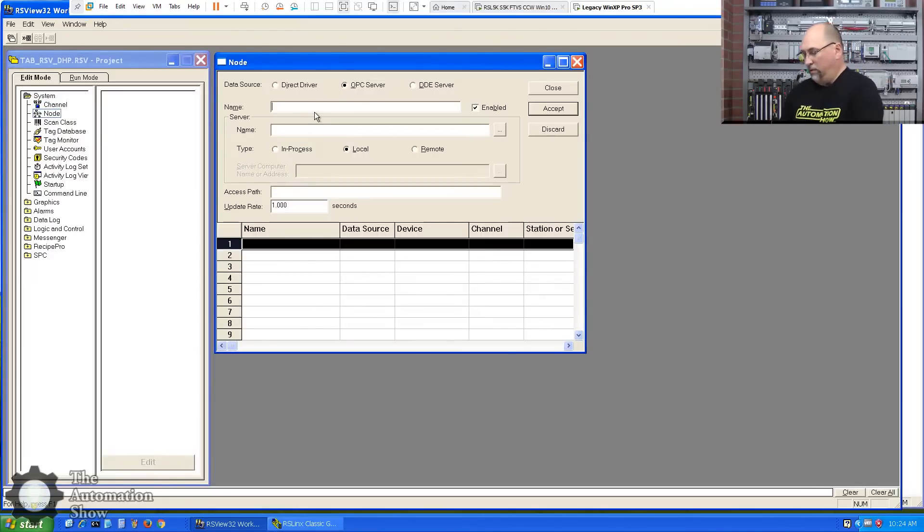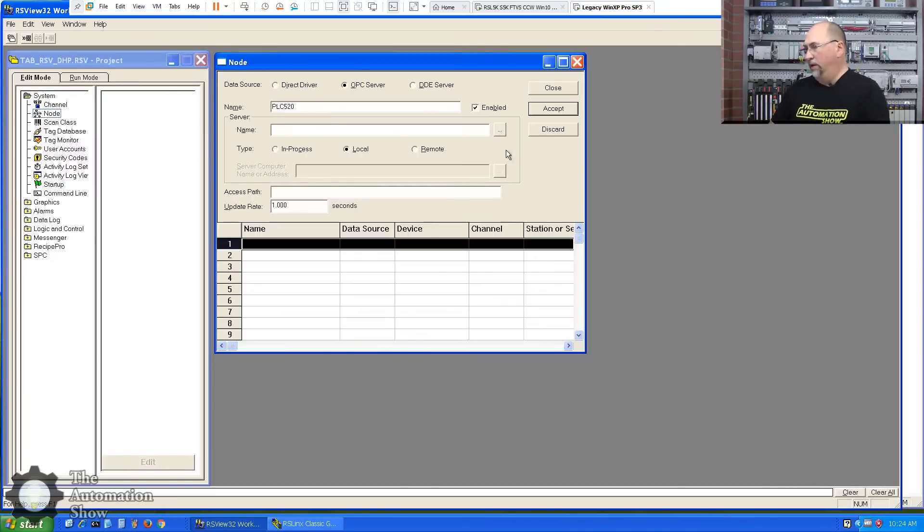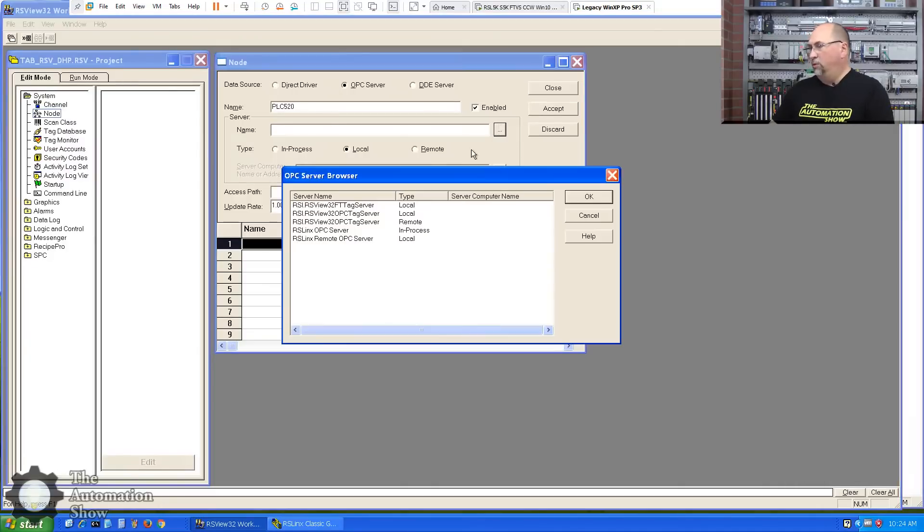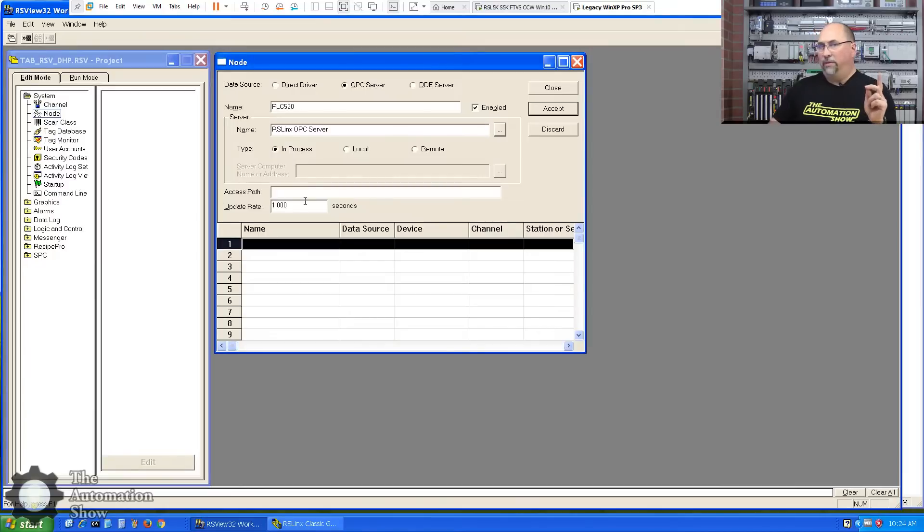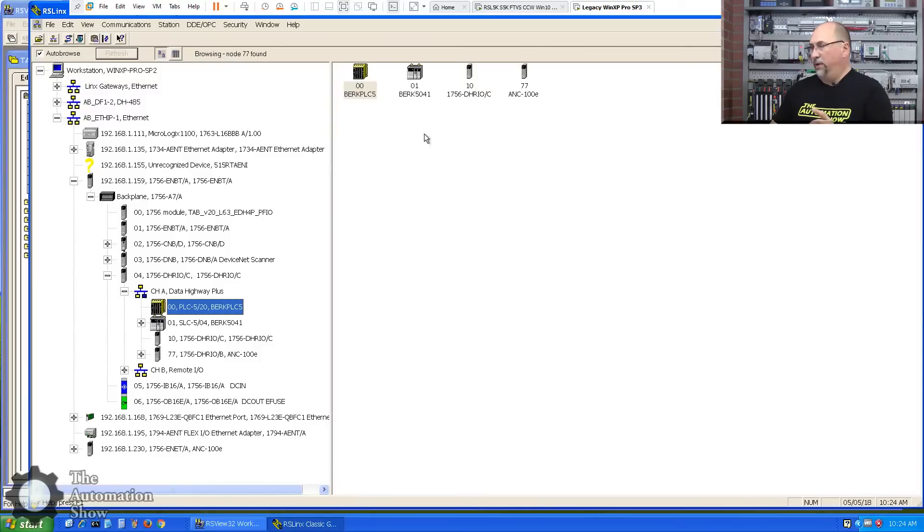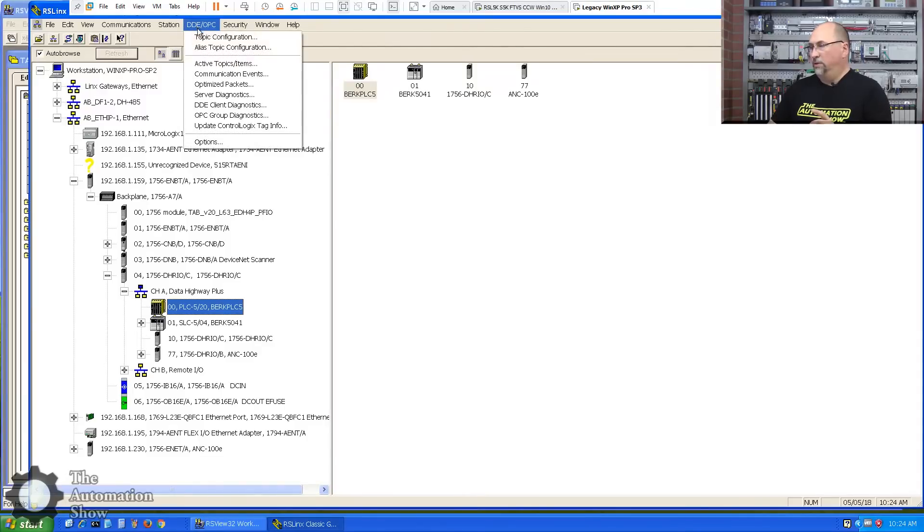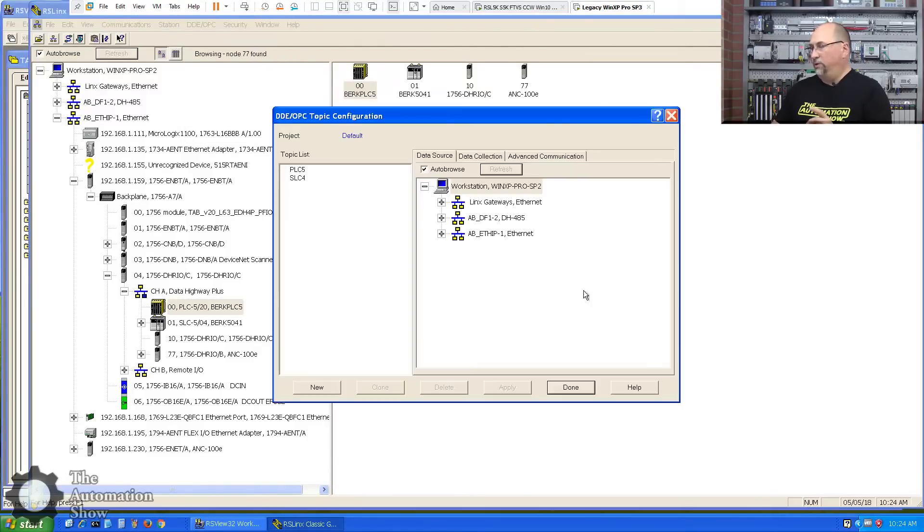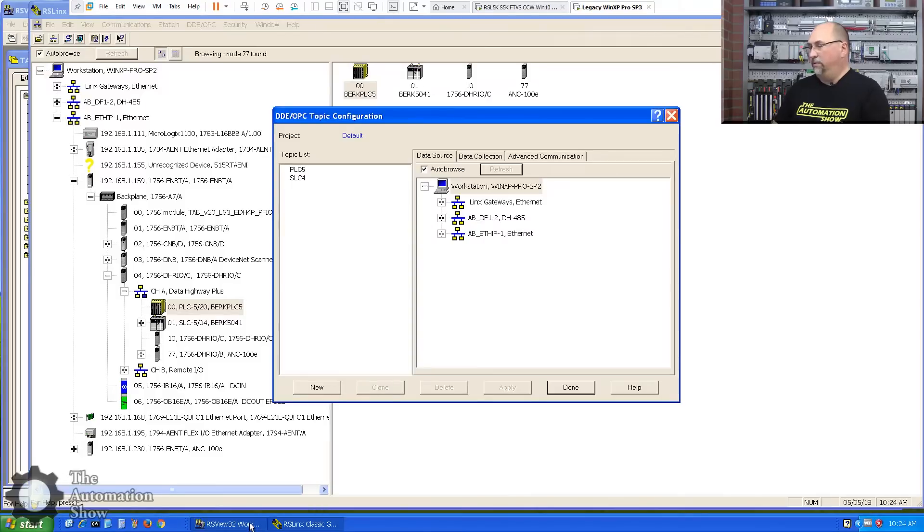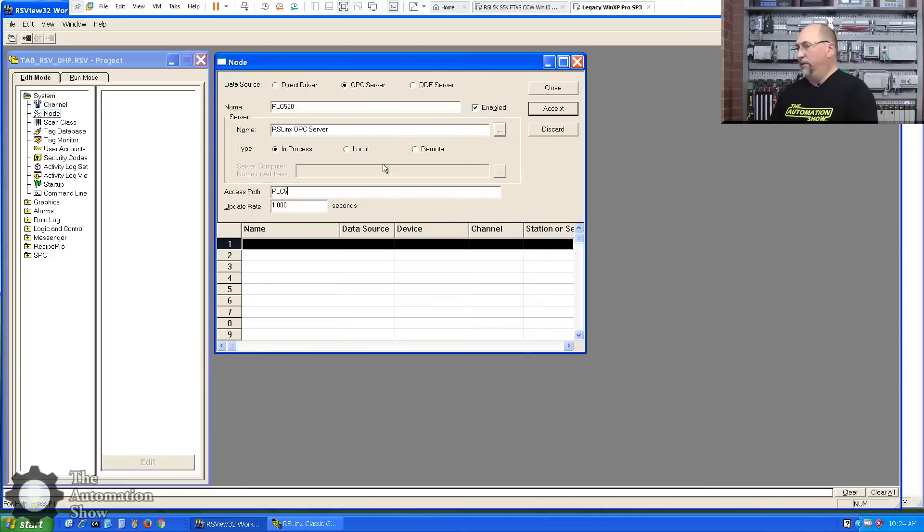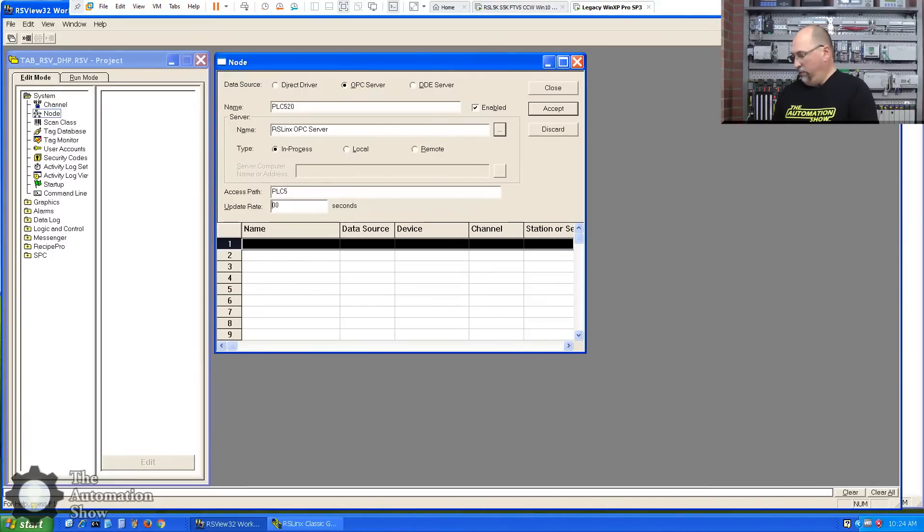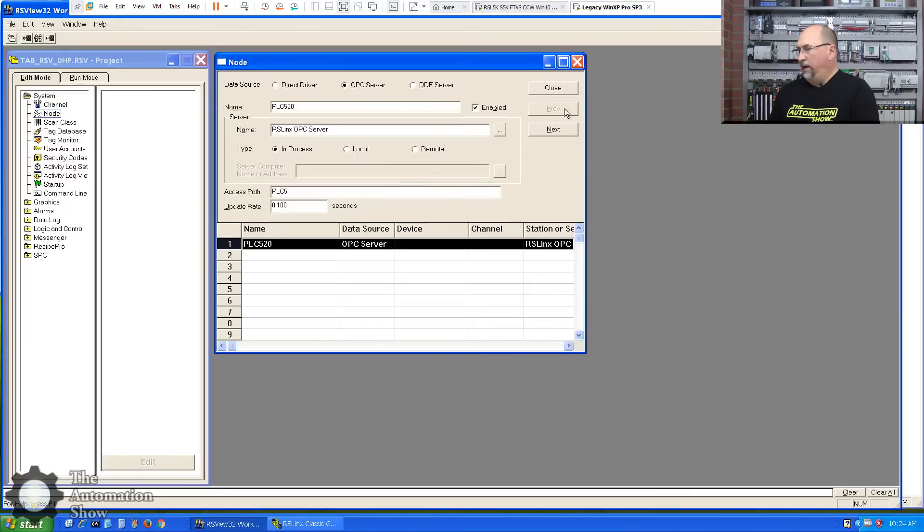We're going to call this PLC520. That'll be the node name. Let's go browse our RSLinx OPC server. And then the access path, this has to be that topic name. Okay. So let's go to DDE OPC topic configuration. PLC5, SLC4. So let's go back to View32. And I will put in PLC5 here for the access path. And again, the update right here, I'm going to put 0.1 seconds. Okay, let's accept that.